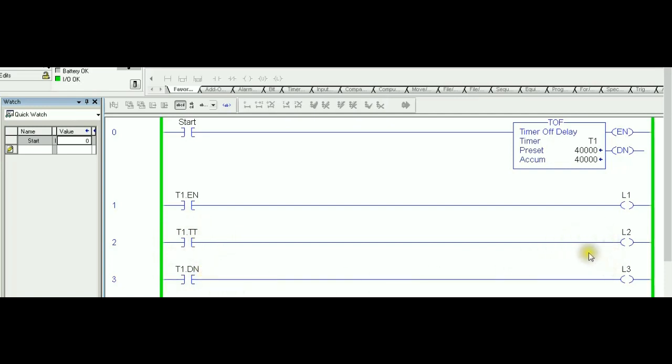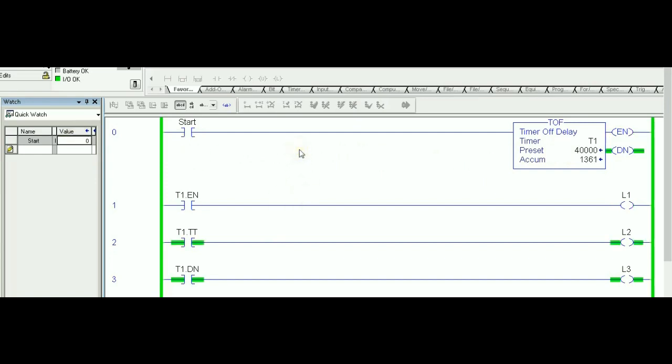So one more time, if I push the start, it's enabled, the timer is reset. Anytime you release it, you break the rung. That's the condition that is required to start and trigger to have the TOF start timing from accumulator equals zero to the preset value.